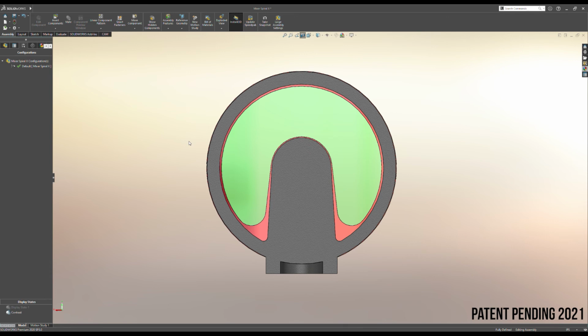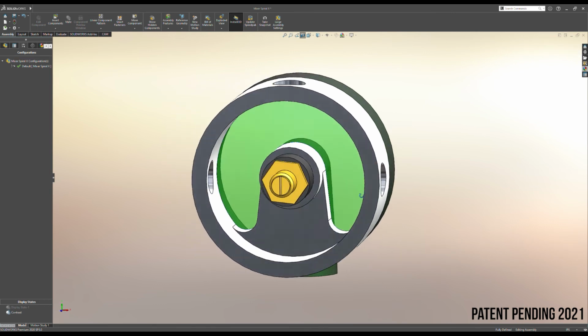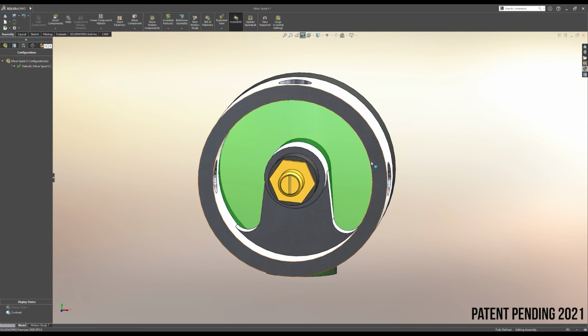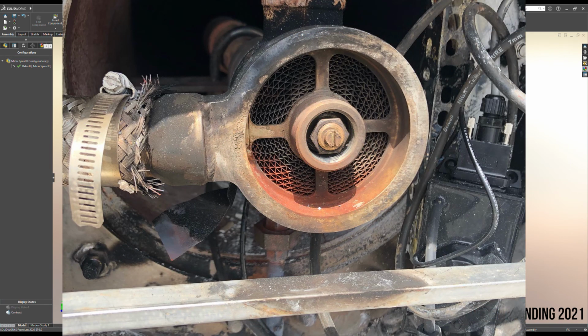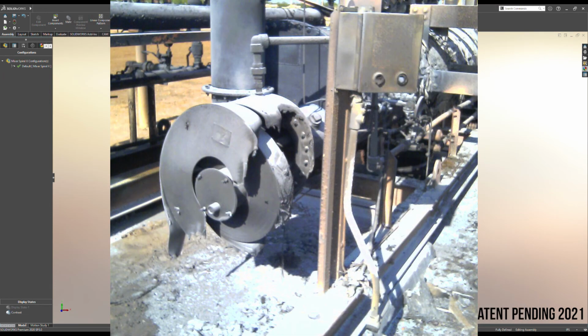Completely aside from the fact that it is far safer to run this fuel ring as compared to other generic fuel rings that run in a fuel-rich scenario. And I could show some pictures that will attest to that. Fuel rings that run in a fuel-rich scenario are dangerous, just to put it bluntly. There have been multiple fires when using these fuel rings. Dehys burned down. It's just a bad deal.